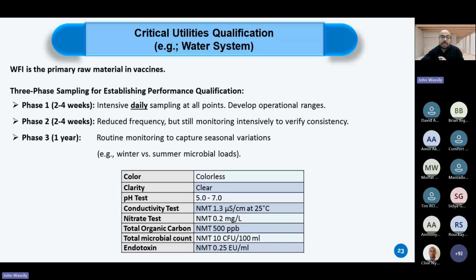Phase 1 is about 2 to 4 weeks. And in this phase, extensive daily sampling for all the water for injection use points takes place. And all the samples are tested for the below tabulated tests. And each test shall meet the tabulated acceptance criteria. The same will take place in phase 2, which is 2 to 4 weeks as well. Here, the sampling frequency could be reduced.